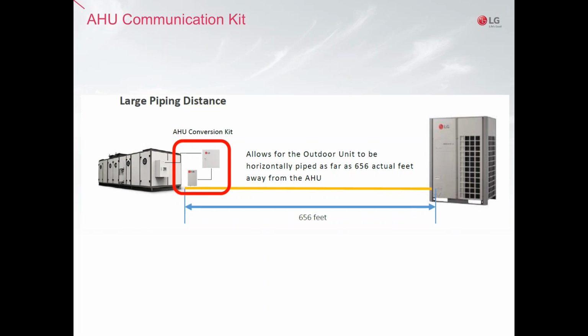Another advantage of using VRF for this application is the large piping distances, which allow the outdoor unit to be horizontally piped as far as 656 actual feet away from the air handling unit. This is a great advantage when you want to keep your condensing units far from the conditioned area, or when you are doing a retrofit of an existing DX commercial split and you need to relocate the outdoor unit way further than what the existing condenser unit will allow.